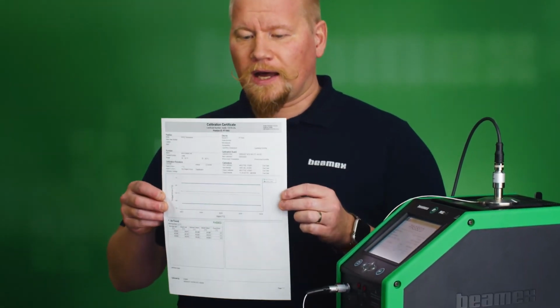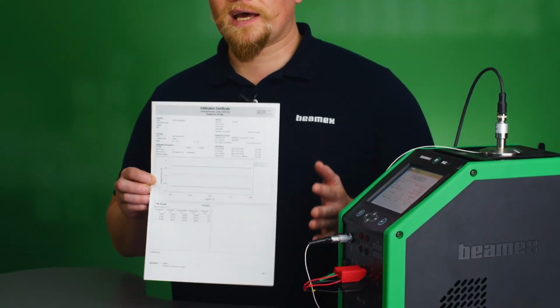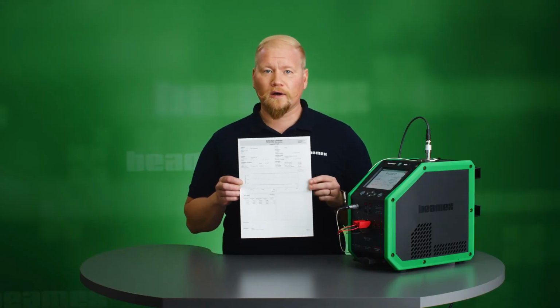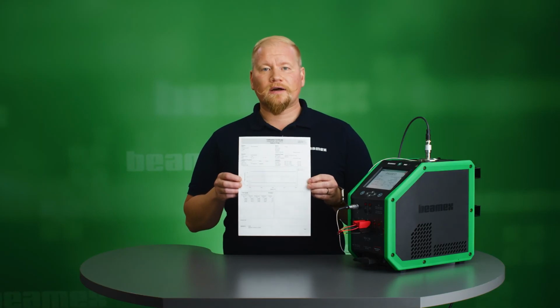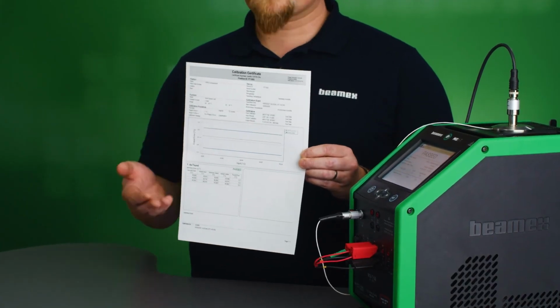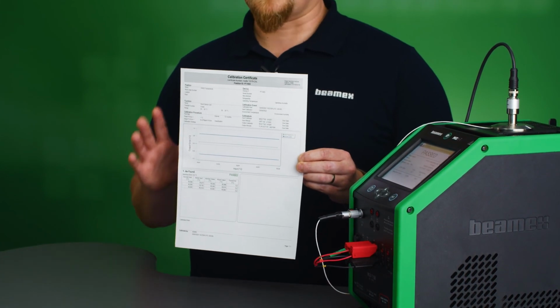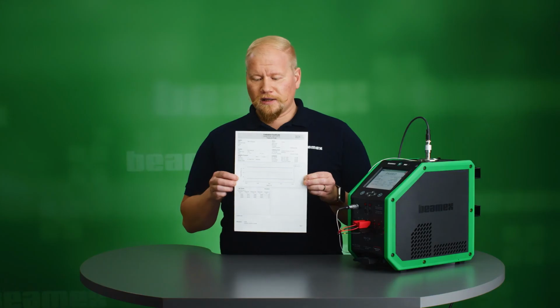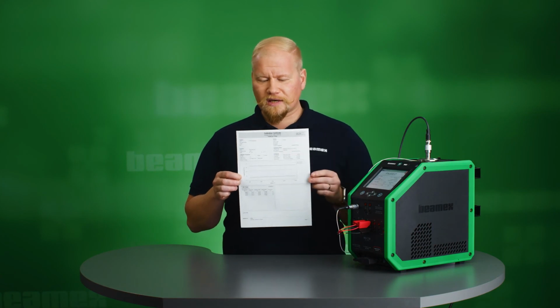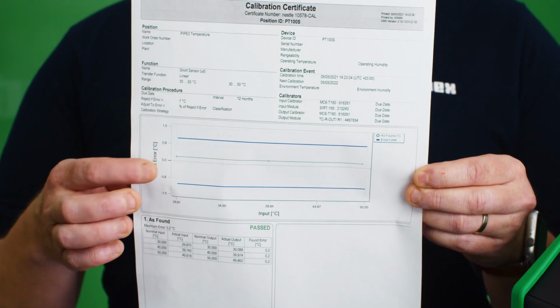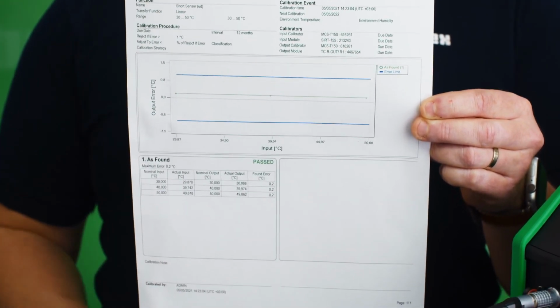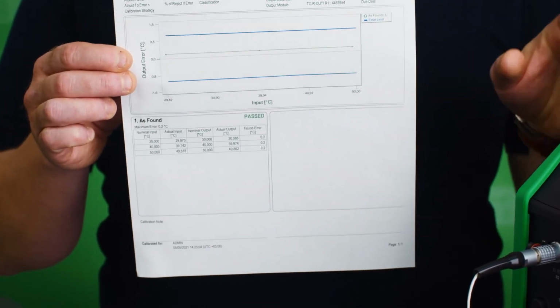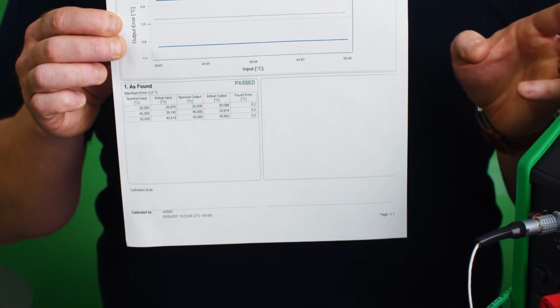I have calibrated, performed my tasks, and I would go back to the workshop to print out the certificate. I have already done that. I could either go completely paperless and keep my data within the software, or in this case, as I have done, print out the certificate. I will then have this approved by my supervisor, have it signed, and the calibration is done and finished. In the certificate, I have all the necessary information needed for traceability. I have my results both in graphical and in numerical view. And if I write any notes while saving the calibration, they will be visible on the bottom side of the certificate.